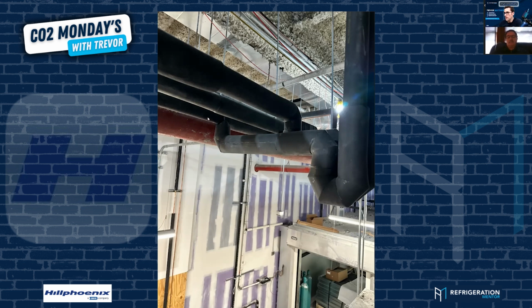Awesome. And so that's why you take this one out, because when I installed a ton of HFC stores, going from the cases, we'd have a trap down at the case, and then we'd go all the way up, just say it's 20 feet. We'd put an inverted trap 20 feet up on top. This one here is going along. This is not going up. This is just going along, and you're pulling off that one. That's why it drops down. So any oil goes down into this trap. Is that correct? That's correct. This is the main return coming back.